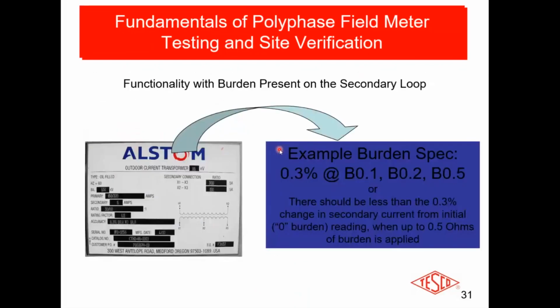And you can see over here, this is that nameplate that you couldn't quite read. And again, several transformer manufacturers, they're all very good. One thing about our industry is anybody that supplies equipment into our industry, they make good stuff. And the reason is our utilities do not accept anything but the best. You guys expect that when you're buying something, it's good stuff. And if you've got a vendor that doesn't deliver that, they're not going to be in our industry for very long. So unfortunately, even our competitors deliver good stuff. Now, they all do. Everybody in the industry makes good stuff.